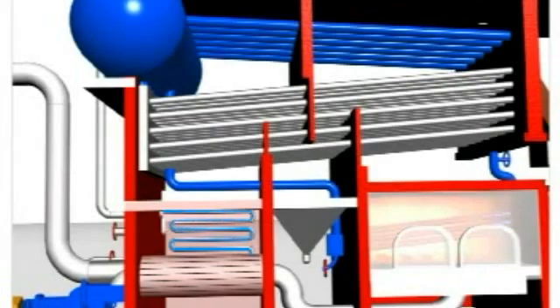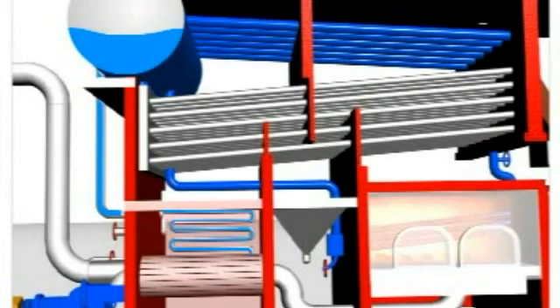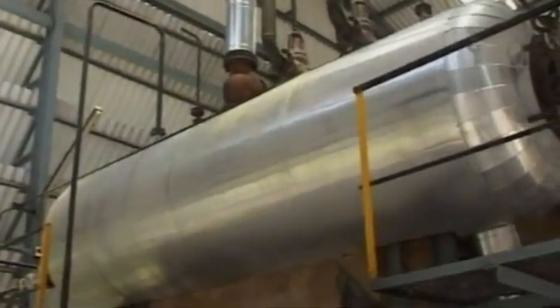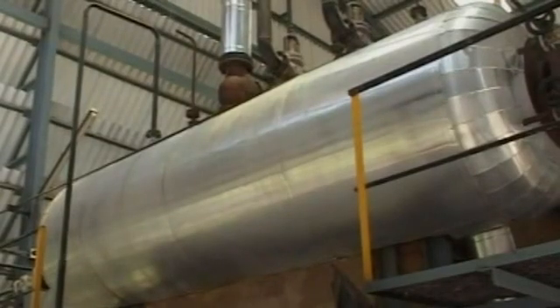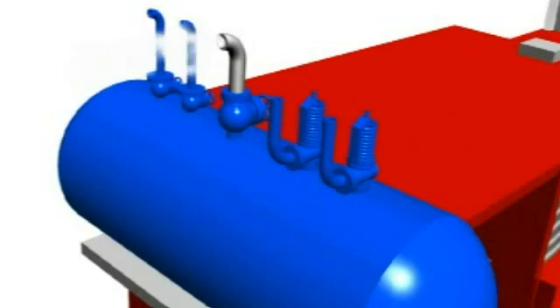From the boiler drum, water moves to the convective bank tubes and radiative furnace in-bed cooling tubes due to thermal gradient. Steam is formed by counter-current convective and radiative heat transfer. The mixture of hot water and steam reaches the drum through riser pipes, and finally steam is taken out of the drum through the main steam valve after passing through the steam purifier.